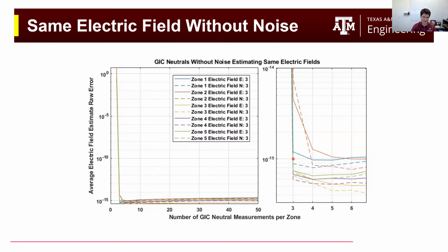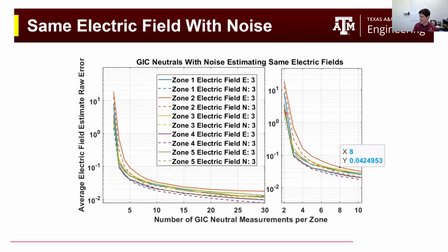But everyone knows that perfect measurements are not realistic. What we were doing is testing the hypothesis that you only need 3 measurements to do this, and the answer is it works. Once you start putting measurement noise in, you reach much more realistic error levels. So the way we did it is we have, in this case, a known E field that we use to calculate the GIC flows in the system.